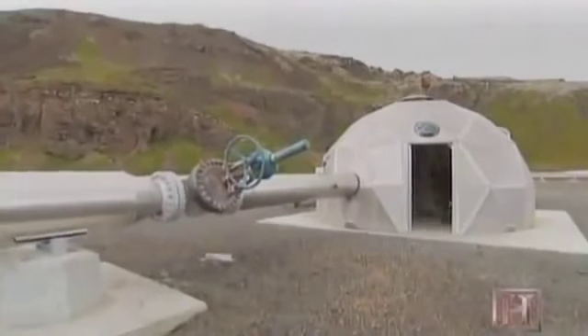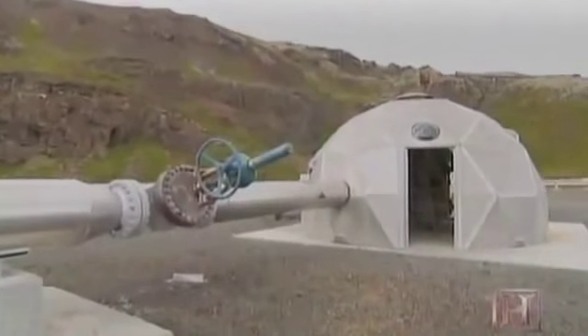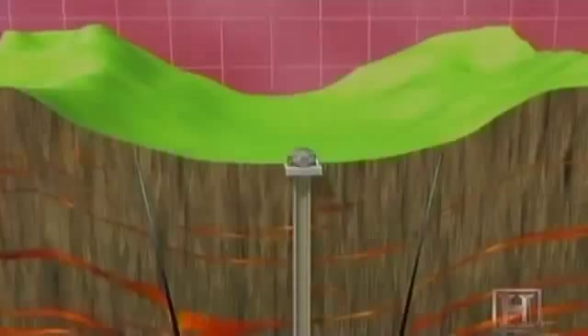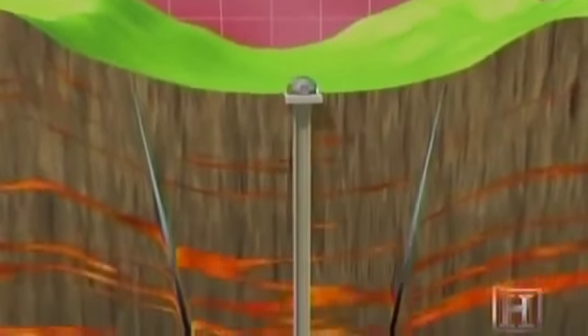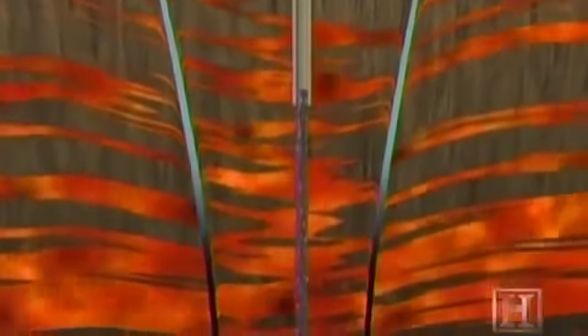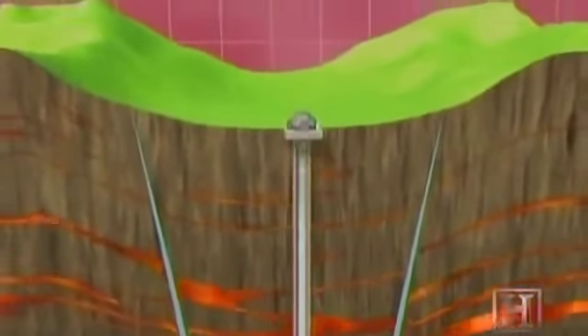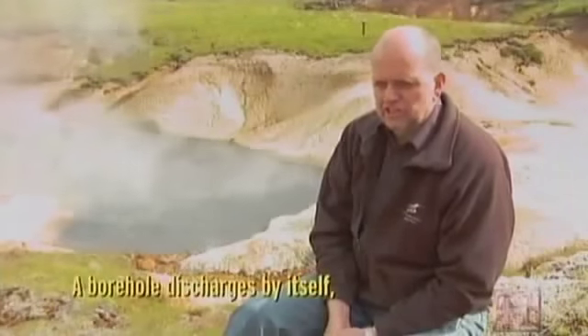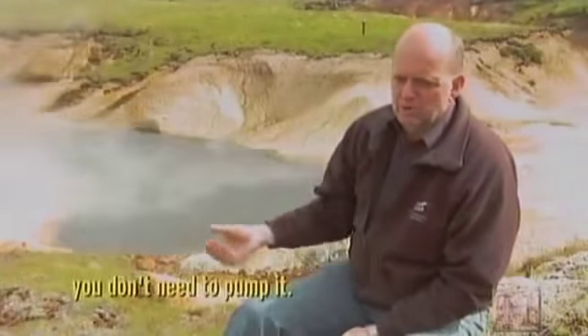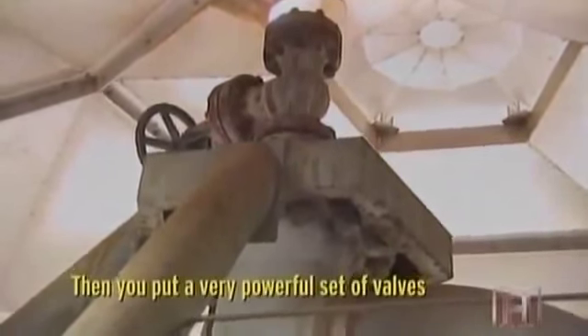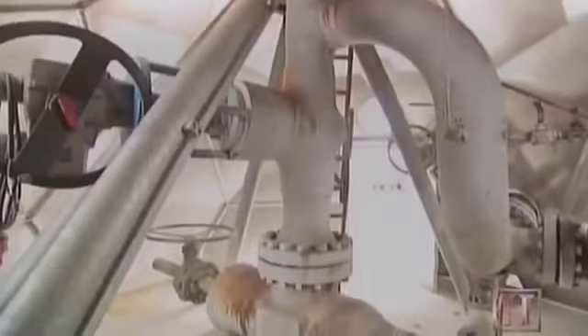Both end products begin here, in one of 15 boreholes drilled as far as 6,000 feet below the surface. The borehole's well is encased in cement to a depth of about 2,000 feet. Below that, the well is lined with perforated metal to let in steam and hot water, which rush toward the surface under great pressure. A borehole discharges by itself. You don't need to pump it. Then you put a very powerful set of valves on the top to control it.